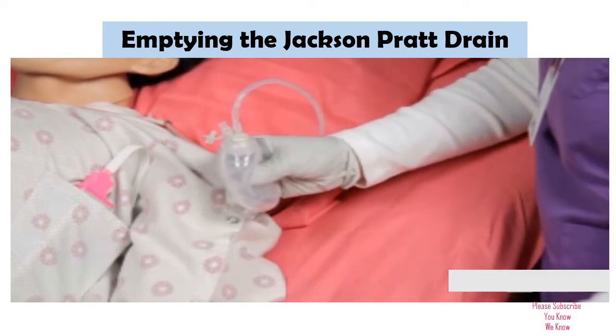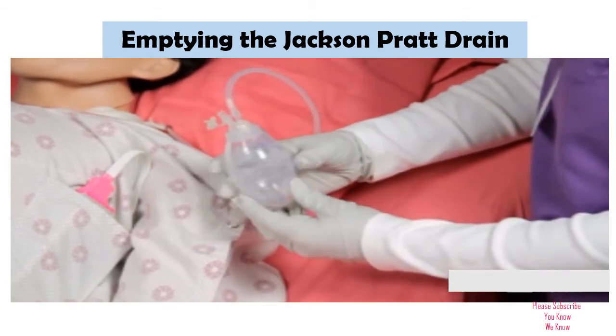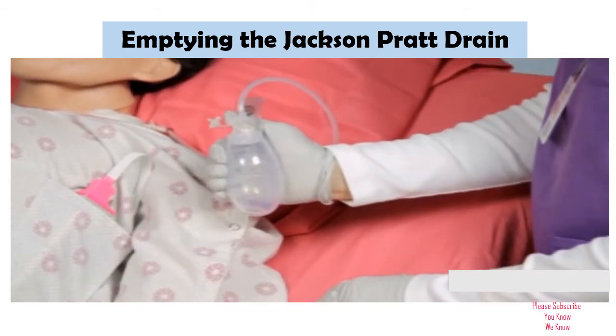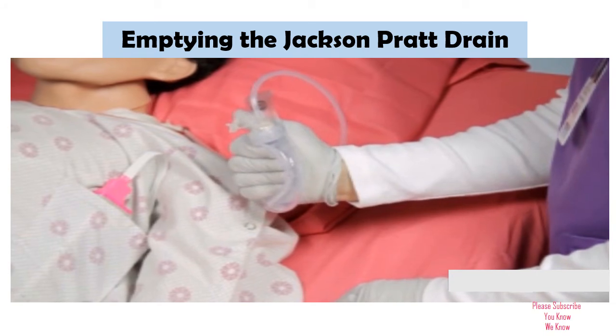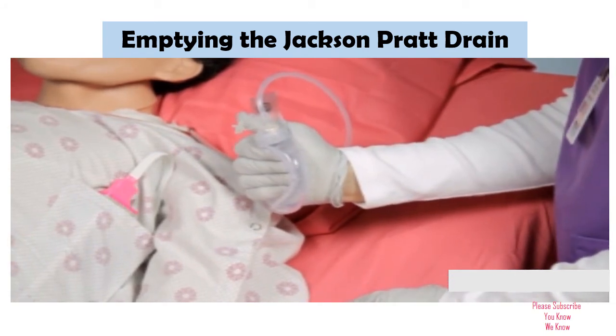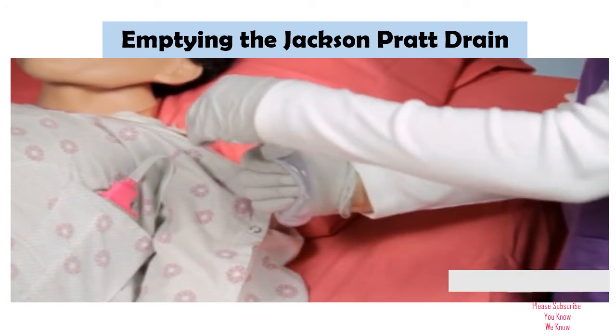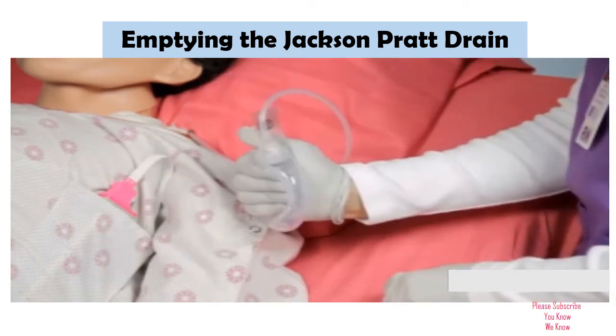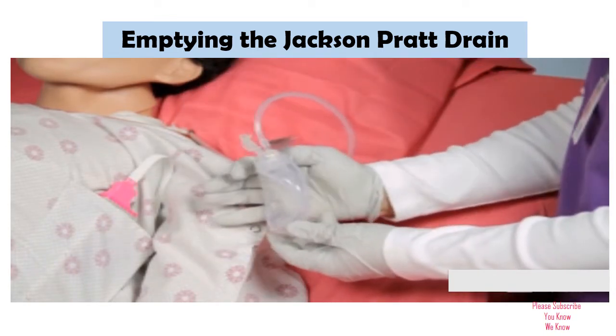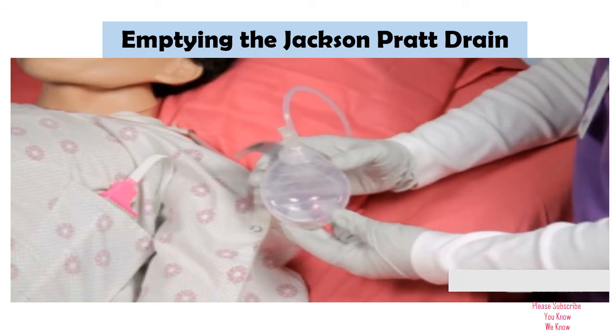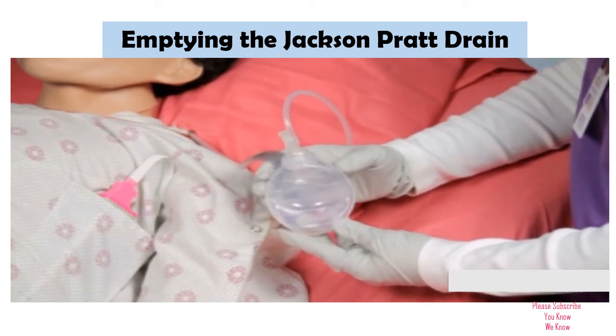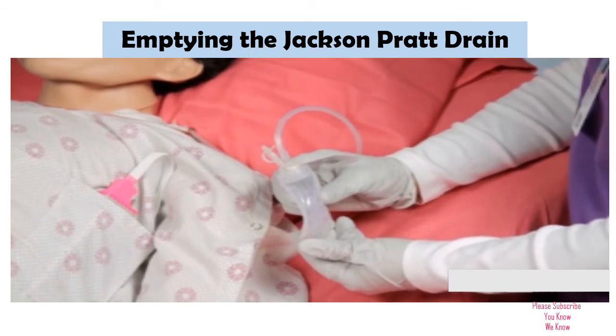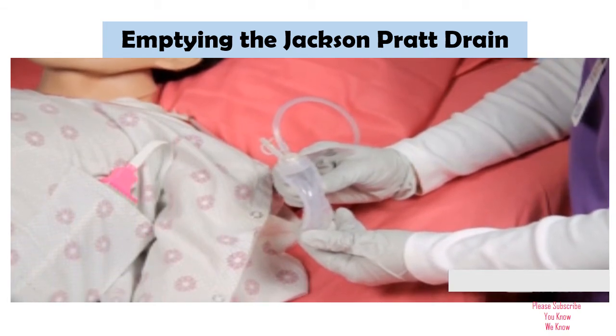To re-establish the suction pressure, first squeeze the bulb in the palm of the hand until the inside walls of the bulb touch. While maintaining pressure, we place the plug and close it tightly. Slowly release the grip to re-establish suction. The bulb should remain concave or somewhat flat. It should not be fully inflated. If the bulb is not flat, suction is not being maintained.